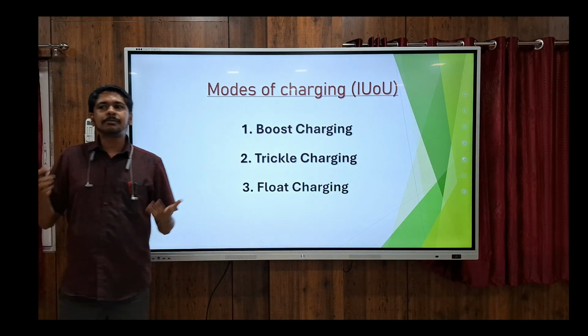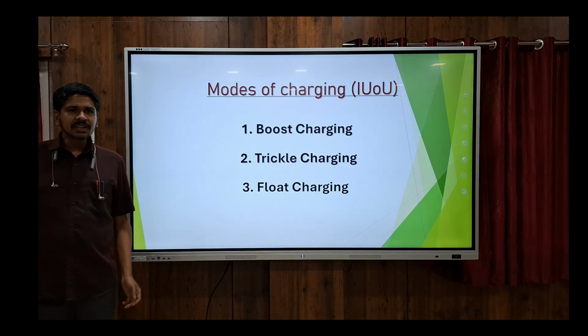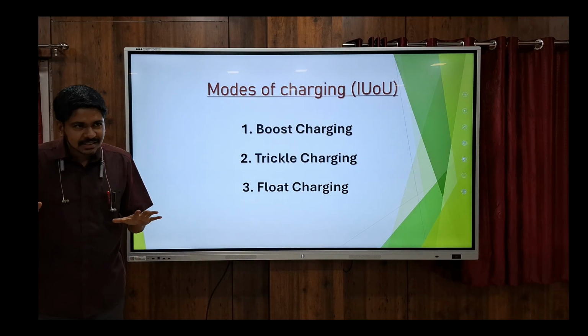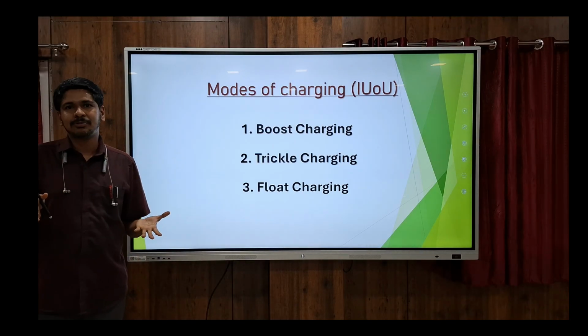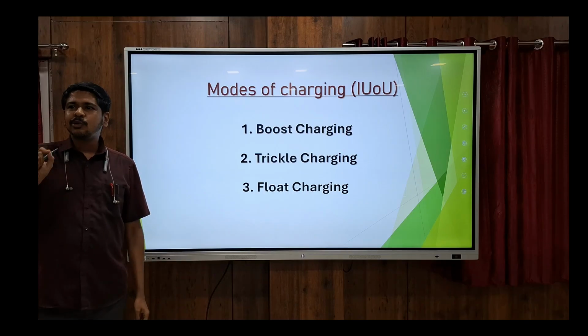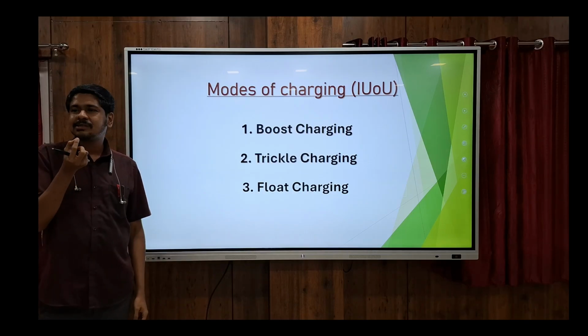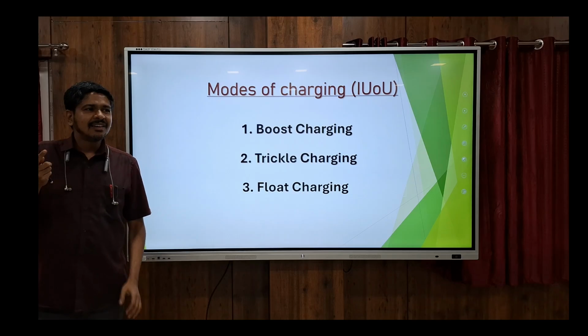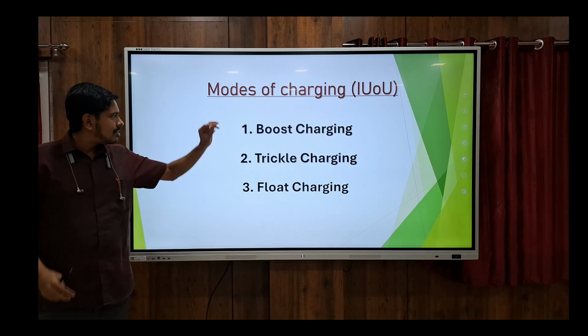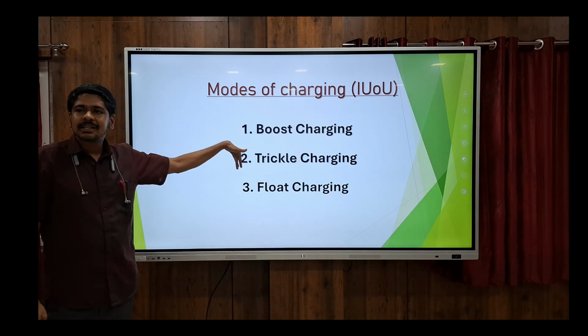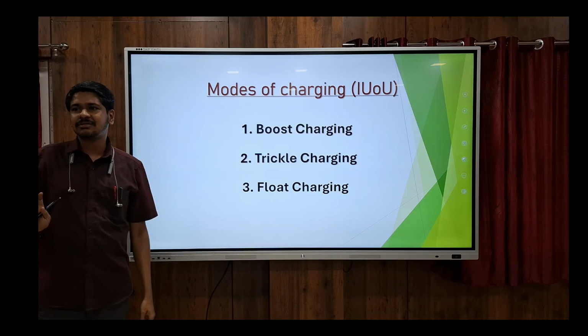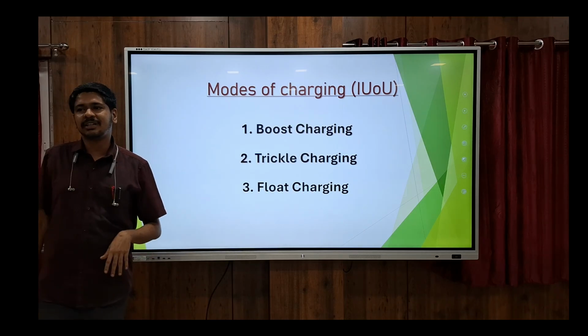In actual concept, there's one more case: if the battery is fully charged and no load is consumed, the drop will only be due to internal resistance or small losses incurred in the battery. Compensating for that requires a current even less than the trickle charging value, but that case is not included in these three modes.